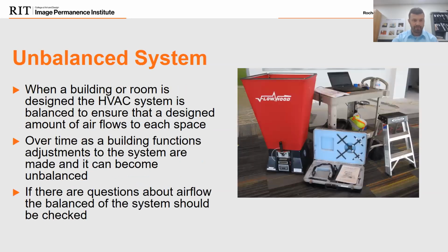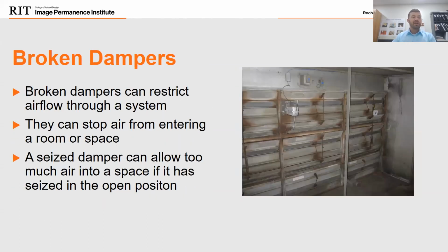Oh, I didn't even talk about this. I apologize. Broken dampers. Broken dampers can restrict airflow through an HVAC system. They can stop air from entering a room. We see this a lot, especially outside air dampers and what they call fire dampers. Fire dampers divide a firewall from one room to the next. They're inside the ductwork. They divide that ductwork at the firewall, and they're designed to close in the event of a fire. And in some circumstances, it's not even poor maintenance, but they just fail over time.